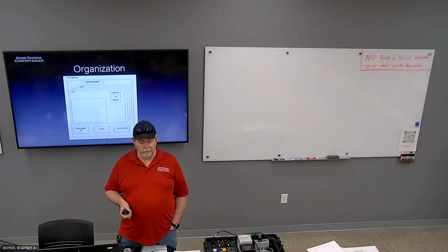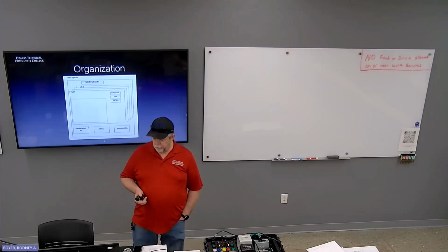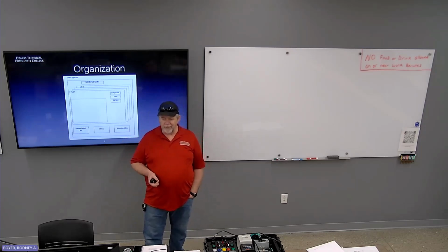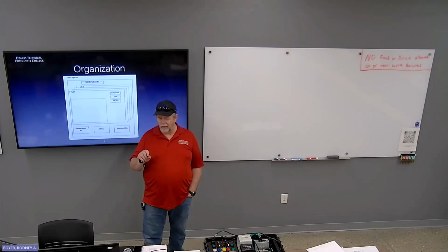Okay. I take it for each task, the watchdog has the same amount of time unless programmed? No. It's based on the size of the program. If you have a task that only has a couple of lines of code in it, it doesn't take near as long to process as one that has a couple of thousand lines of code in it.